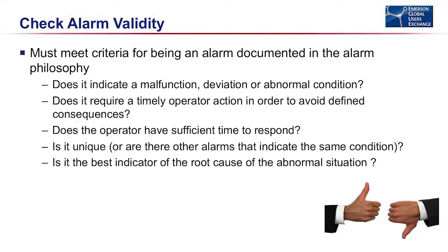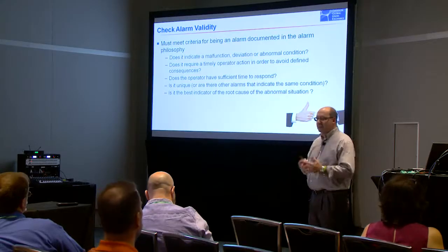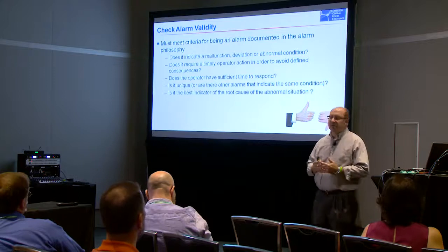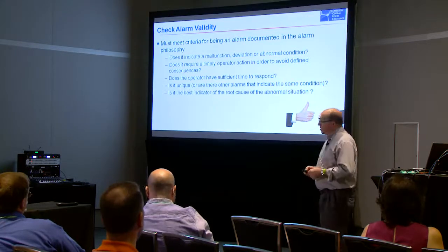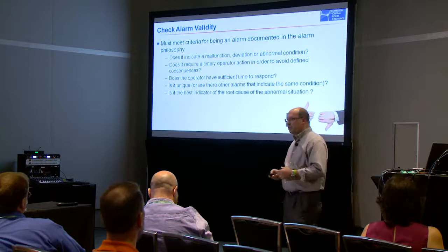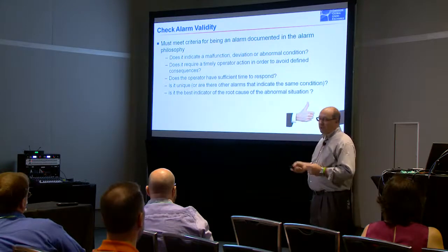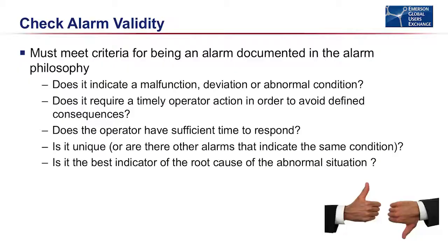Define some criteria to put into your philosophy that you can apply over and over again in a consistent fashion that will help you weed through whether something is an alarm. Take the emotion out of it. Take the subjectivity out of it. So this is an example of criteria that's been recommended and used and you all could use in your plants. So you would ask for a given alarm that you're looking at: Does it indicate a malfunction, deviation, or abnormal condition? You can see that relates directly to the definition of an alarm that we talked about. Does it require timely operator action? Does the operator have sufficient time to respond? You get the idea.